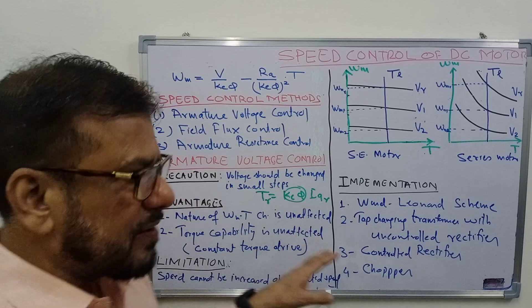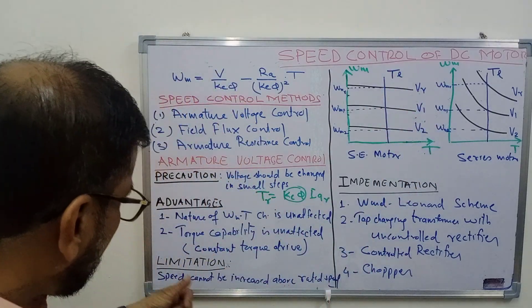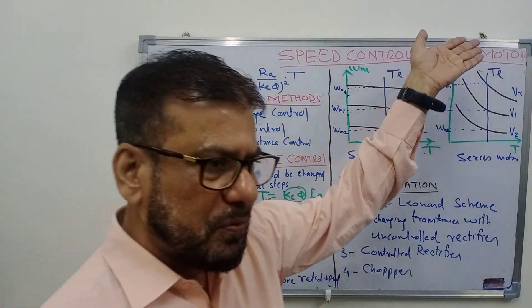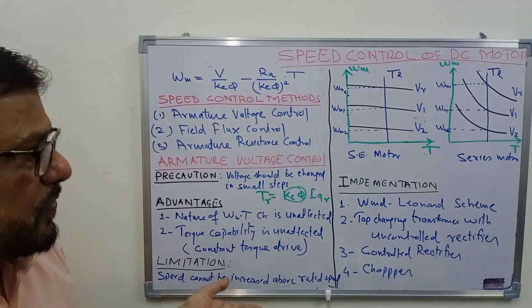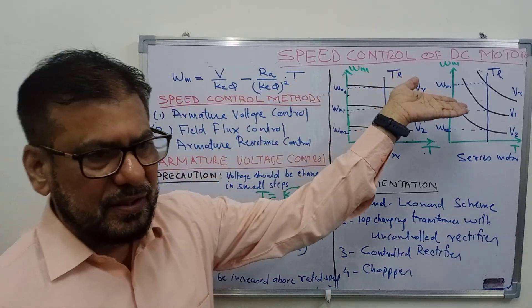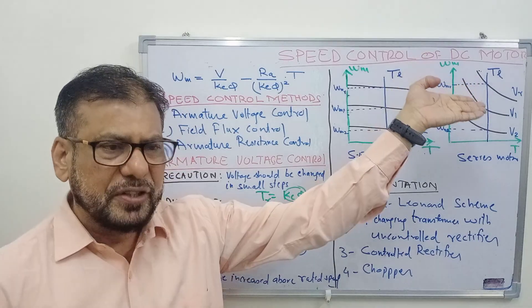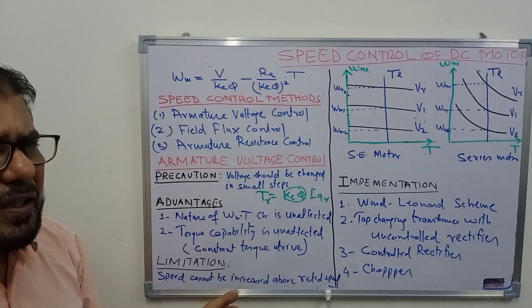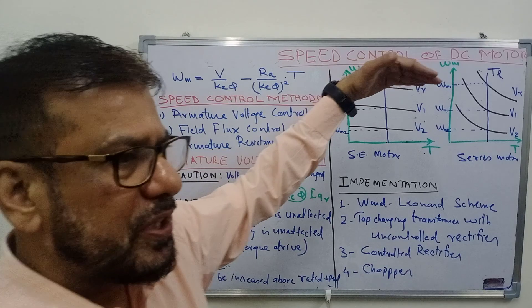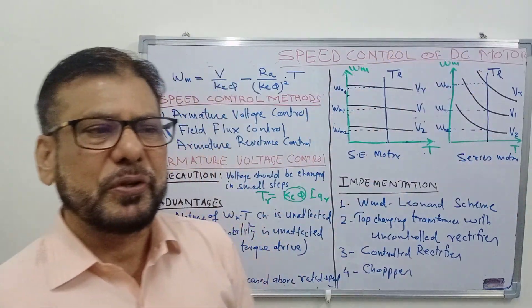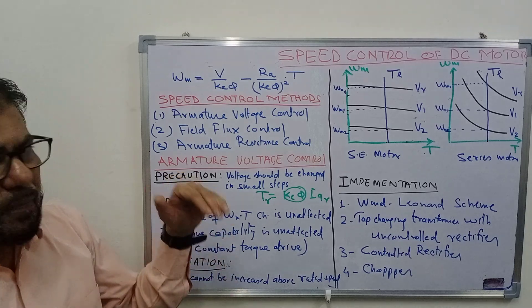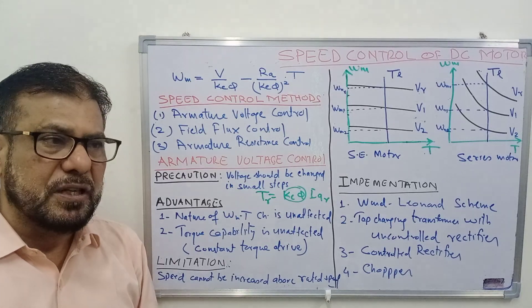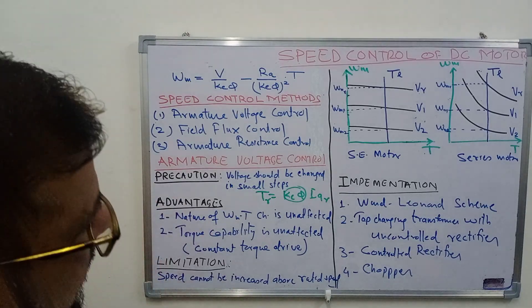That is why this method is the most commonly used method. The limitation is that you cannot increase the speed above the rated speed, because you cannot raise the voltage substantially above the rated voltage — perhaps only 10–20% at most. So speed control above rated speed cannot be achieved with this method; you must consider another approach.